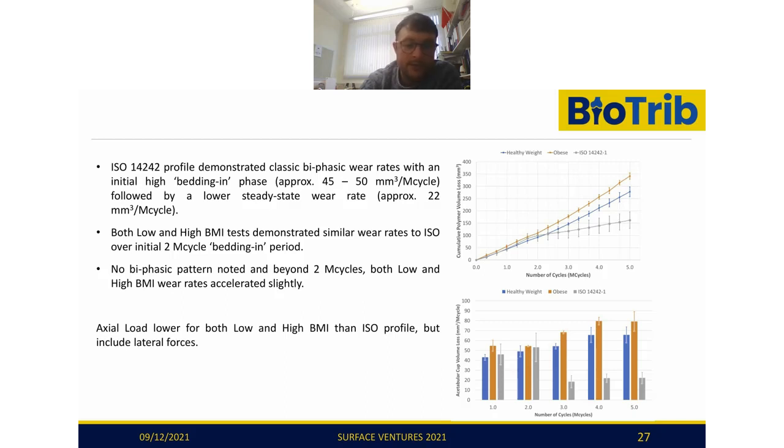But with these patient-derived profiles, we don't see that. If you squint enough, you may be able to argue that you're actually seeing an uptake in the wear rate as it progresses. So again, loading in these situations isn't everything. Ultimately it comes down to the kinematics and the motions that we're applying to these devices.